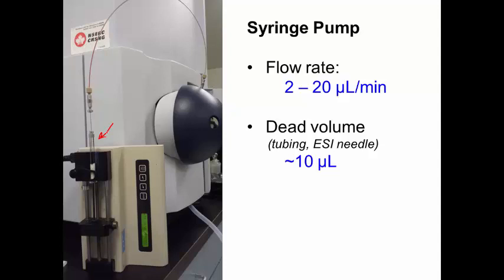The flow rate will be set really low, so you can set the dials here. You'll see this when you actually go to run these experiments, but the flow rate should be set somewhere between 2 and 20 microliters per minute. The sample will travel down this tube and ultimately into the instrument.